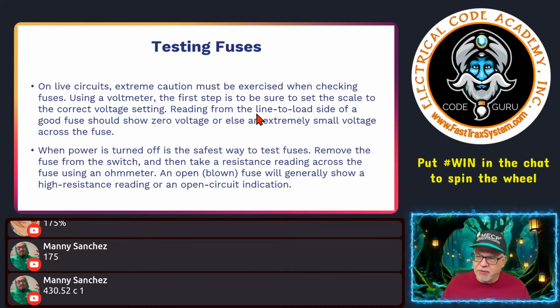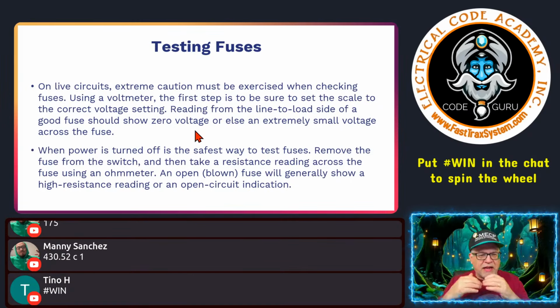Now, reading from the line to load side of the good fuse should show 0 volts or, on an extremely low voltage scale, close to it. One way to test a fuse is to check from one side to the other, and you should not see any variation in your voltage. So if you're doing, let's say 120, you're checking one line of a 2-pole fuse set, then you check one lead to the grounded conductor or even to ground, and the other lead to the actual line side of the fuse. You'll get a voltage reading. Then check to the load side, you get a voltage reading, okay? Same thing on the other, okay? And that way you know the fuse is good, that type of thing.